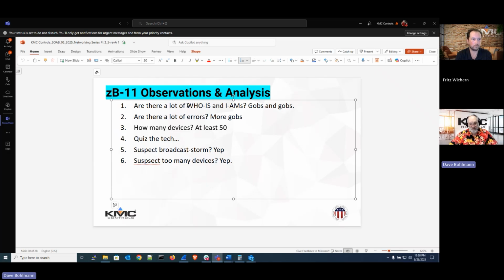There was quite a number of Who-Is and I-Ams, and if we would look at that in detail, then that could give you a hint of whether or not there really is a broadcast storm. But the first thing I would do is tell them, look, you've got too many devices. Check your end of lines.